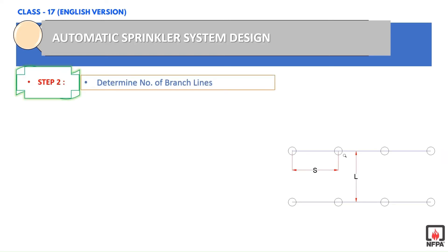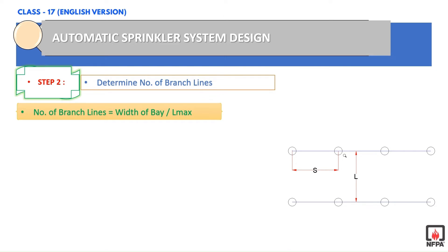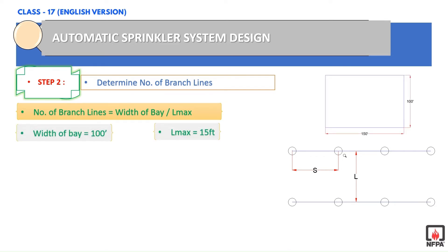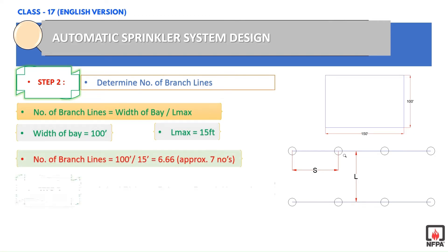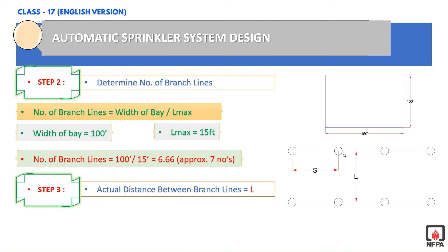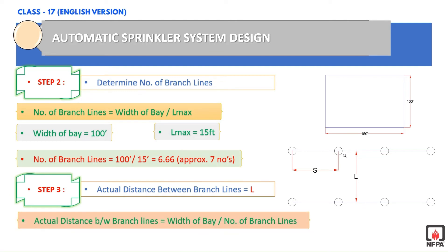Step 2: The formula for calculating the number of branch lines is the width of the bay divided by the maximum distance between sprinklers (Lmax). Here, the width of the bay is 100 feet and Lmax is 15 feet, so the number of branch lines will be around 7. Step 3: We calculate the actual distance between branch lines (L), using the formula: width of bay divided by number of branch lines. The actual distance between branch lines will be around 14 feet.